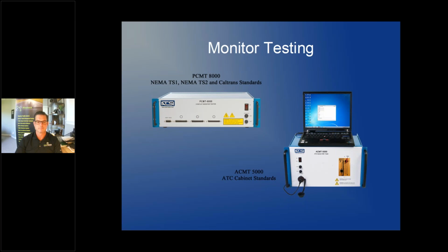Currently we have two different monitor testers. The PCMT 8000 is the latest in a long line of testers, going all the way back to 1988, when we started with NEMA TS1. Later NEMA TS2 was added, and then Caltrans. We used to have separate models for each one; currently one tester can do all those models. You can see there are connectors on the front—we have different cables for connecting whatever types of monitors you have. The monitors tend to have different connectors, or they're in a completely different format, such as the Caltrans or 170 style. We can get you whatever cables you need for that.